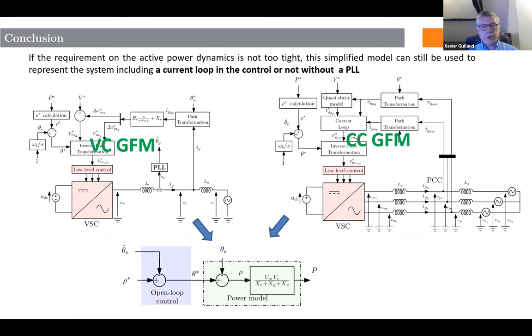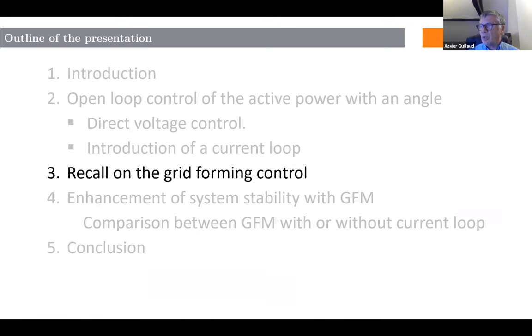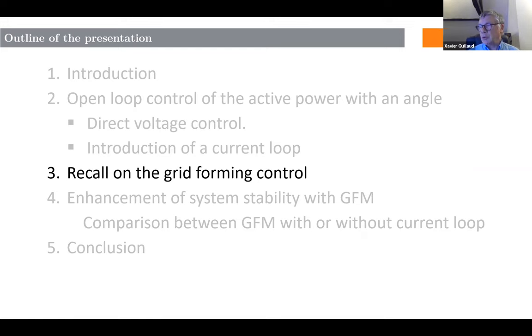We define two types of converter control: voltage-control grid-forming (VCGFM) and current-control grid-forming (CCGFM). We can assimilate the behavior of both systems to this very simple model drawn from the static model of the system. It is not an extremely accurate model obviously, but if we don't move the active power reference too fast, this model is enough, and from it we can derive the controller for the active power.